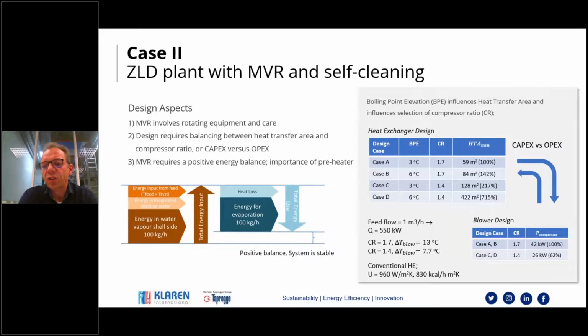And the other side of the coin is that if you choose a compression ratio of 1.4, then the temperature increase over your blower is only 7.7 degrees. And if you go to 1.7, this temperature increases to 13. Temperature difference is directly the driving force of the heat exchanger, so it's directly related to the heat exchanger area that you need.